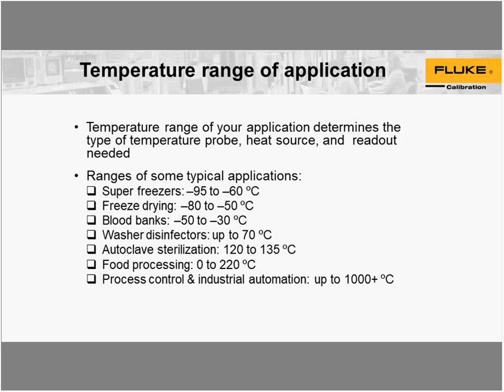All right. So we need to have a couple of things ahead of time. We need to know what the range of our application is, what temperature range we need to run our calibration through. Some typical ones out there have different ranges. Super freezers, cryo, -95 to -60, freeze drying -80, blood banks from -50 up to -30 degrees, disinfectors around 70 degrees, autoclaves, food processing and process control instrumentation all above zero, and they can get quite high in temperature.